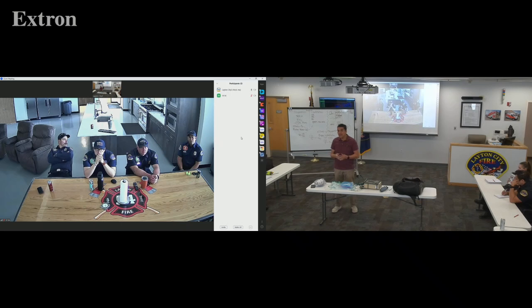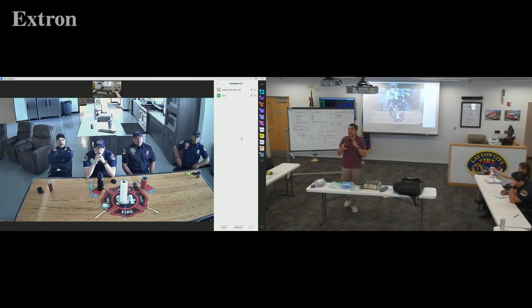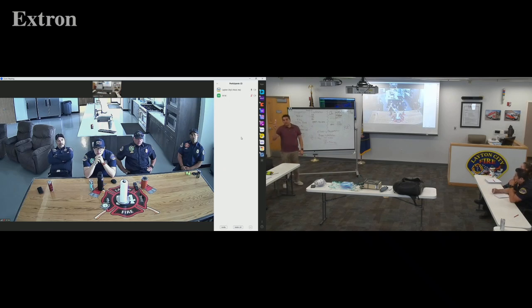The problem with that is that when you do that, it allows them to exhale for a longer period of time, but sometimes it doesn't provide the full tidal volume that you set because there's not enough time. So you have to be mindful of when you use that I time. It's directly related to the rate that you set. If your respiratory rate is too high, but your I time is too high too, it's never going to get the tidal volume that you told it to give.